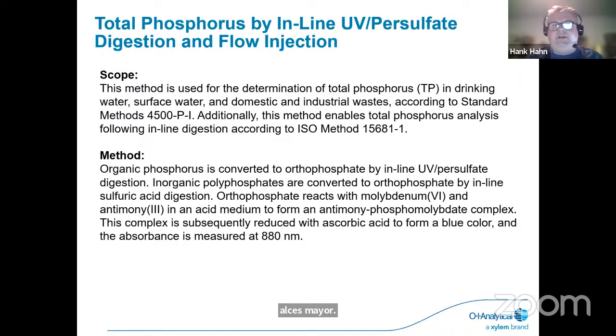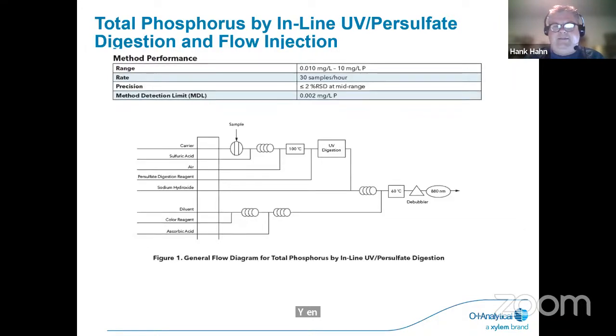And we have total phosphorus as well by inline UV persulfate digestion and flow injection. So this eliminates the distillation step for total phosphorus. And again, this is using heat and UV digestion. We use a combination of flow injection and segmented flow in this, as this again is one of the complicated chemistries. Both of these require a few more pump tubes for the setup, but they do allow you to eliminate the digestion step by doing inline apparatuses.